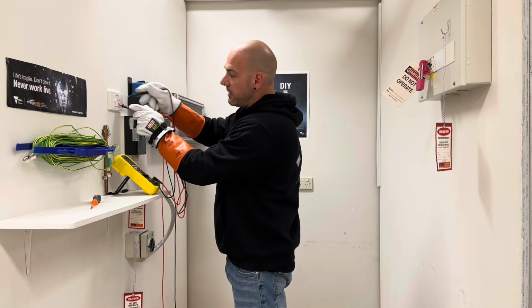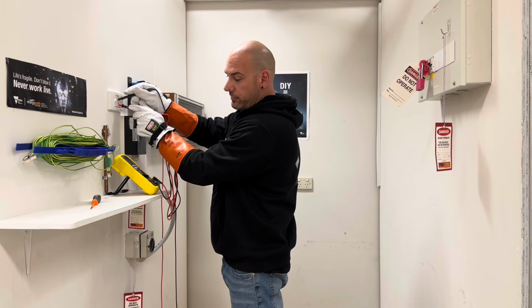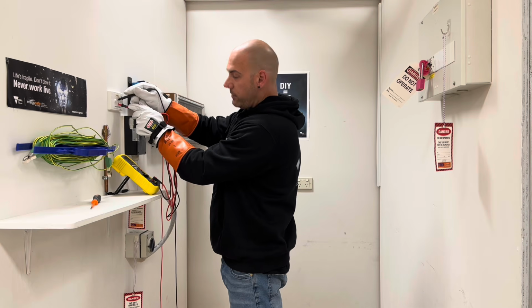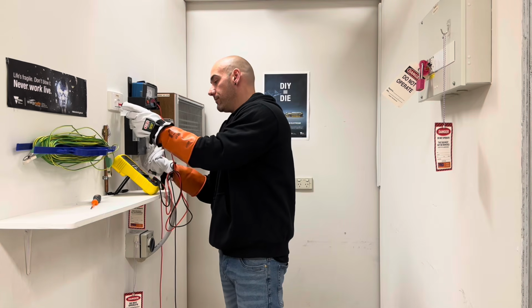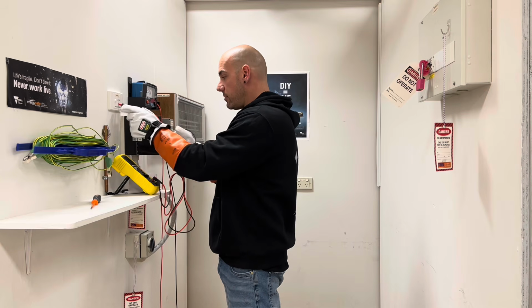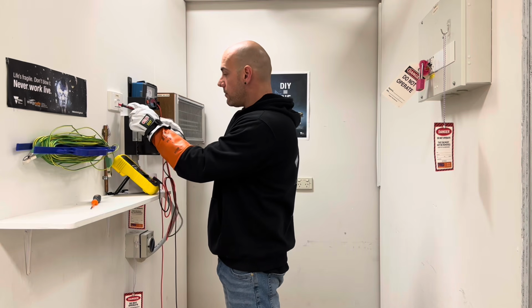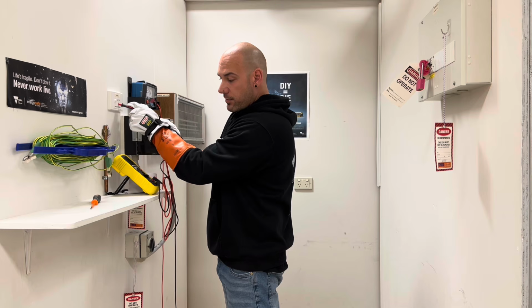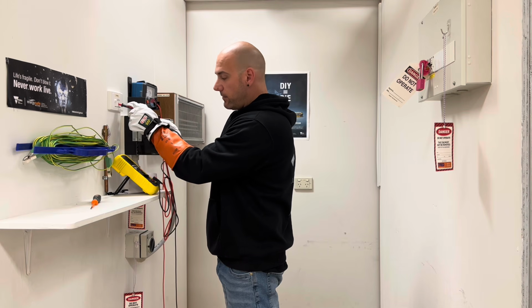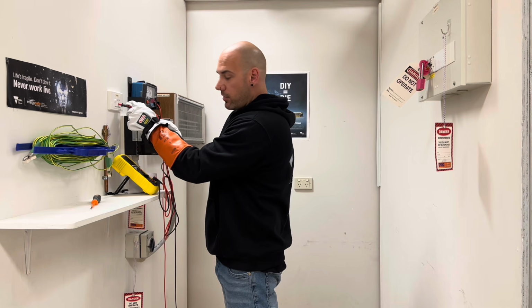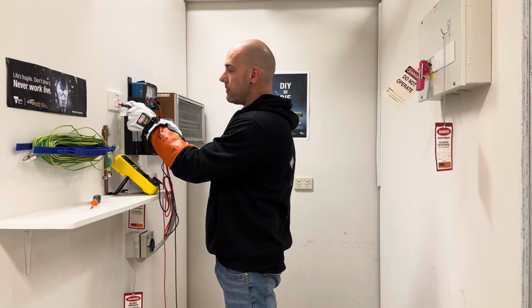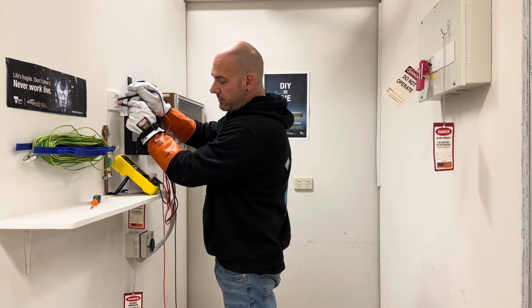We will test our tester on our reference voltage, and we have 24 volts there. Go inside the J box and test from earth to earth. 0 volts, earth to active, 0 volts, earth to neutral, 0 volts. Test our tester, at 24 volts, so that's working.